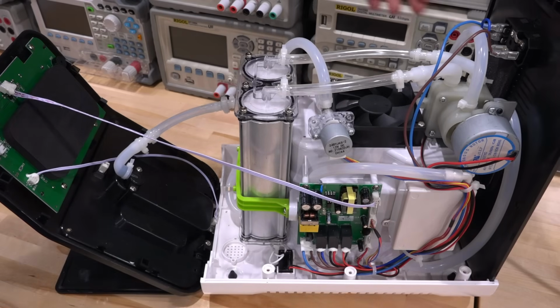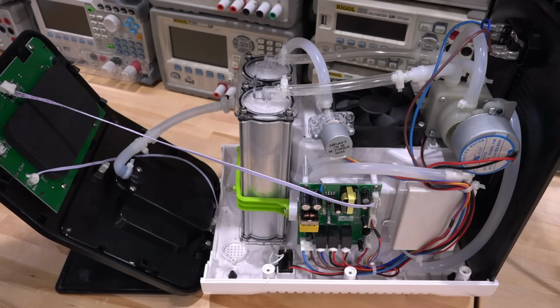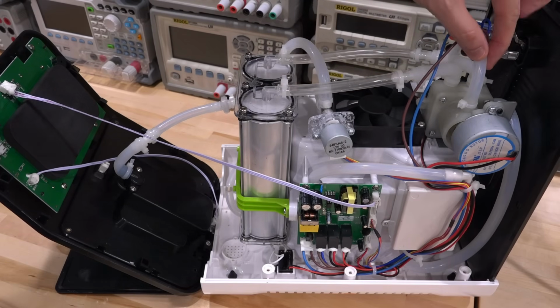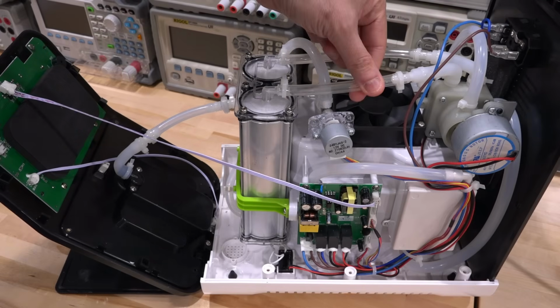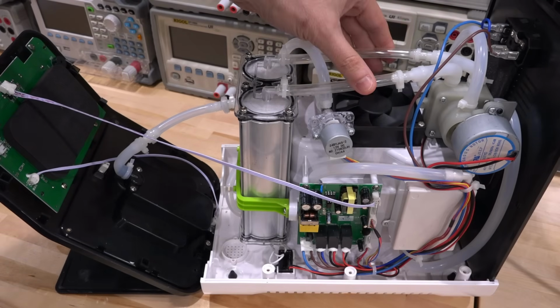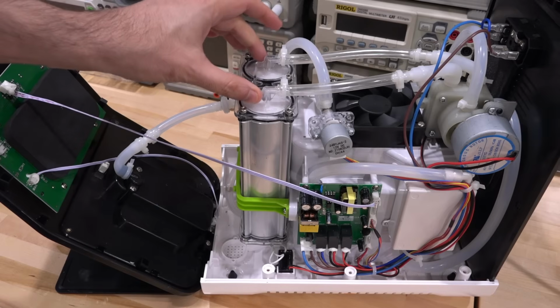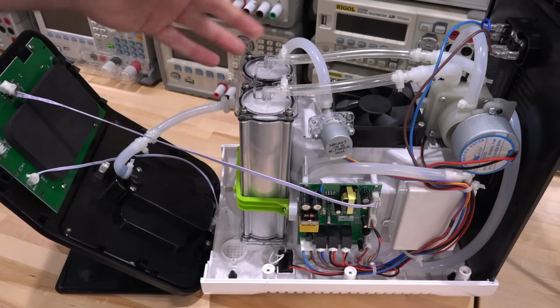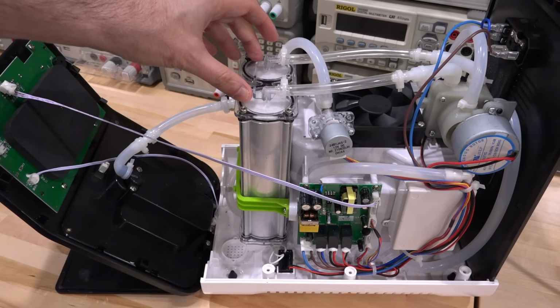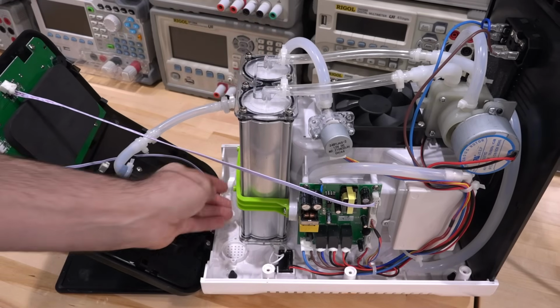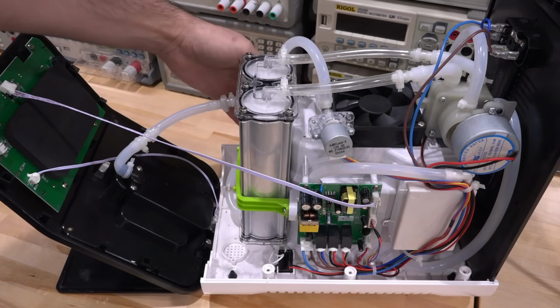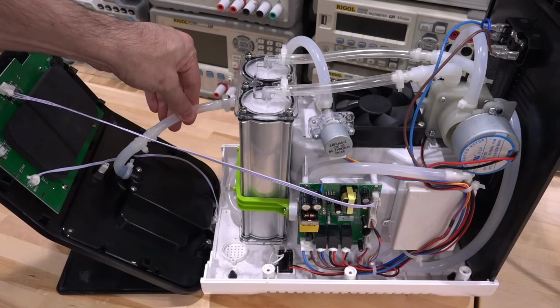On the other side, this is the compressed air coming out, and it goes into this valve over here. This is basically a motor connected to a valve which should constantly rotate, switching this compressed air from this hose into this hose back and forth, just like we explained before. And those are going to go into our zeolite containers over here, which are a molecular sieve. And the oxygen concentration is going to be achieved from the bottom over here, from this pipe. And this pipe comes over here and it goes in the front of the unit.